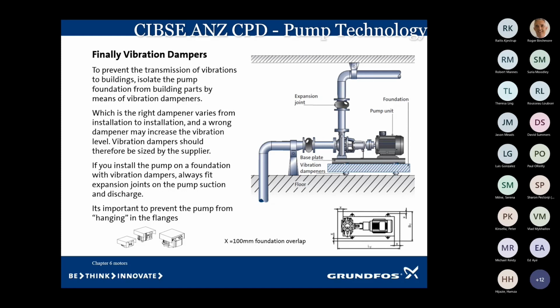The inertia base is a concrete pad which is 1.5 times the mass of the pump and the motor. We then put vibration dampeners underneath that. So now, if there's any vibration, it goes into the concrete pad. It doesn't get transferred back up into the pump and the motor, and it doesn't get pushed past the dampeners. And this will lock that vibration in on that system quite happily.